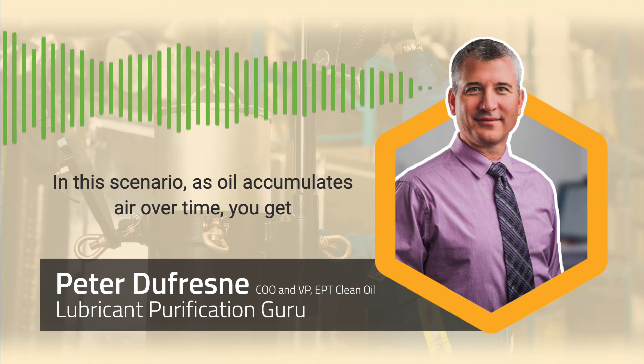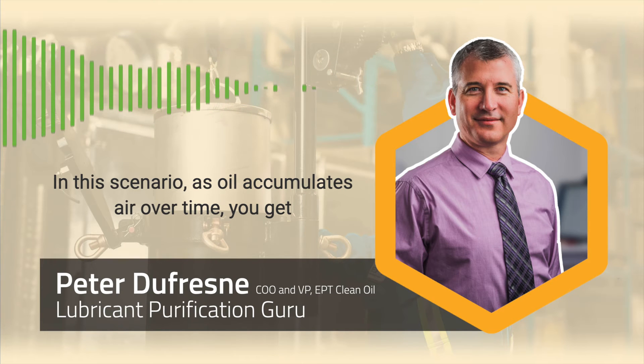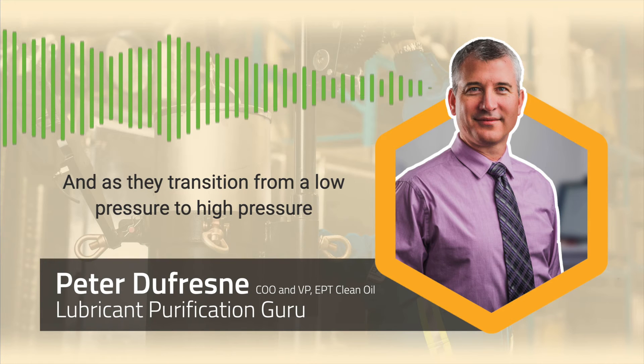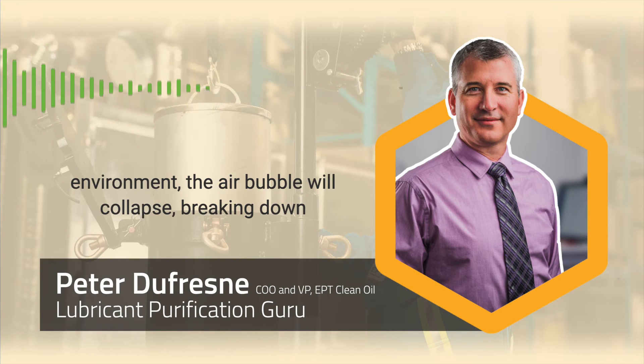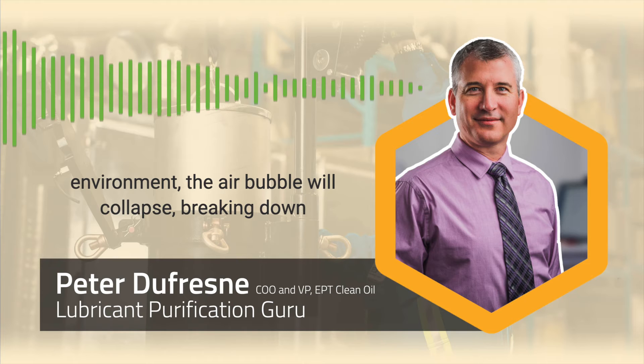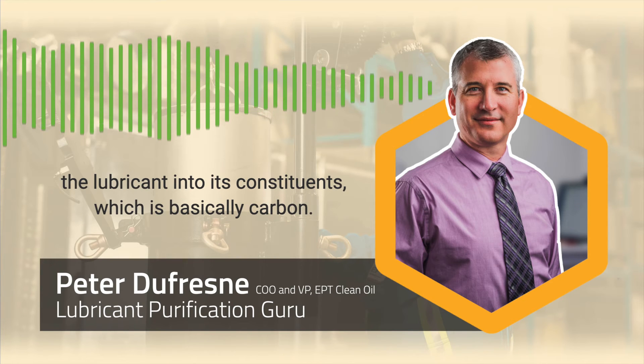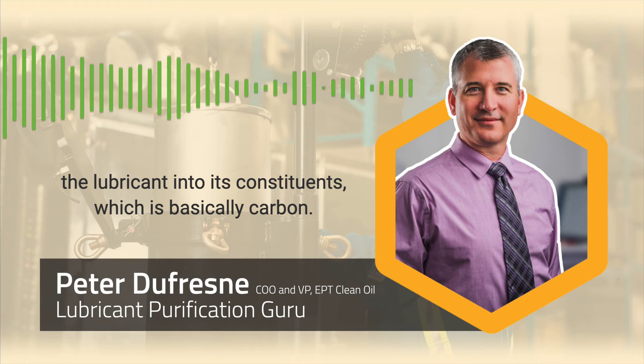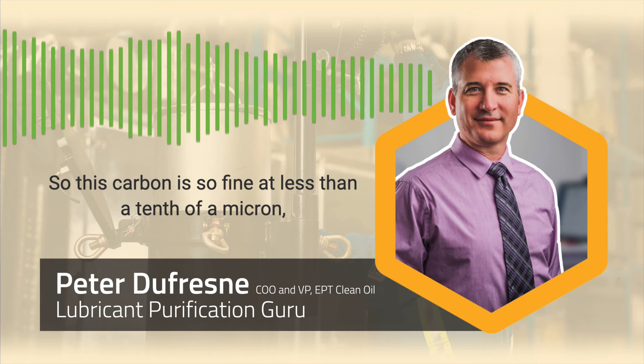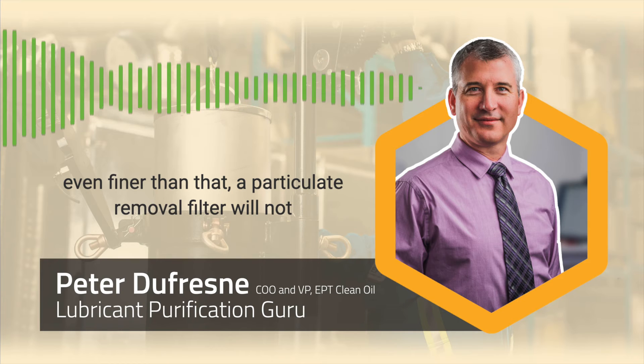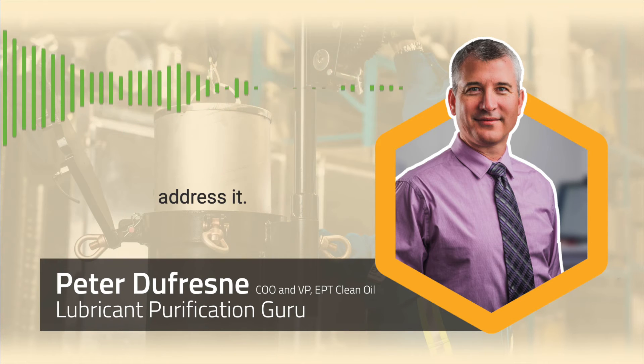In this scenario, as oil accumulates air over time, you get air bubbles going through the high pressure pumps. As they transition from a low pressure to a high pressure environment, the air bubble will collapse, breaking down the lubricant into its constituents — basically carbon. This carbon is so fine, at less than a tenth of a micron or even finer, that a particulate removal filter will not address it.